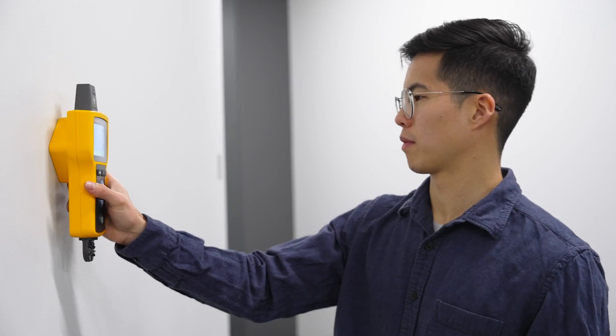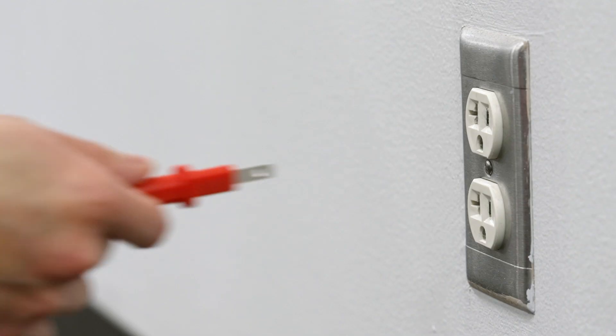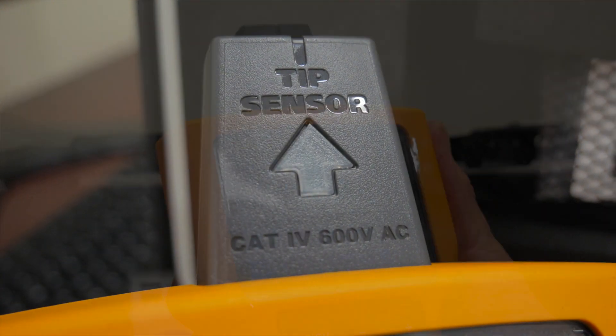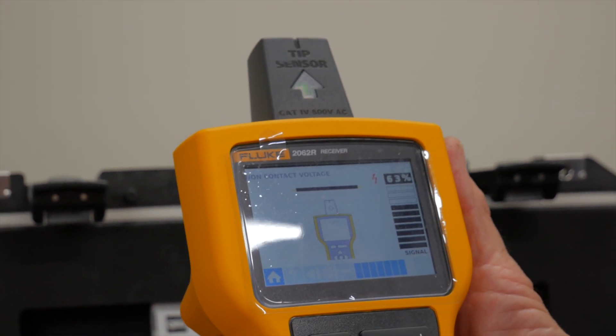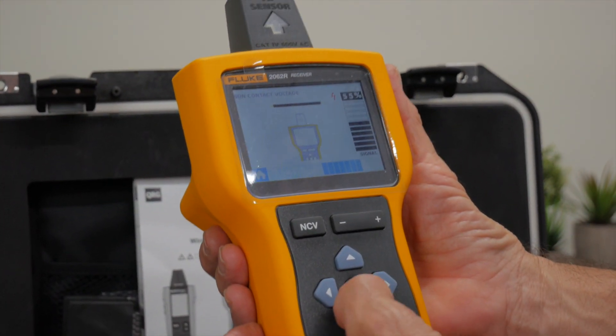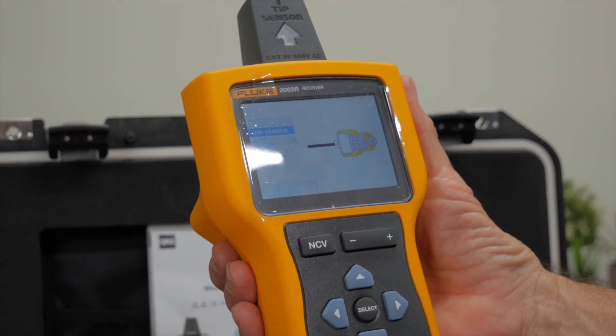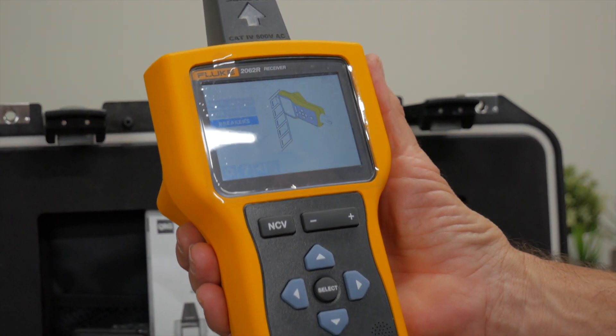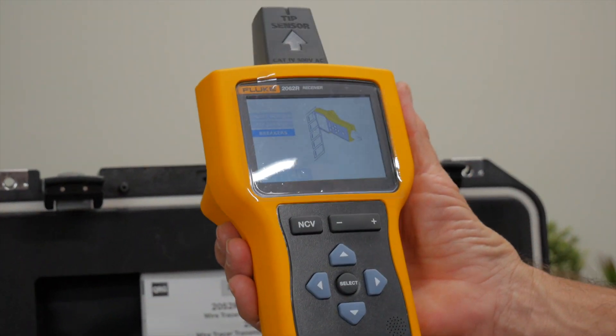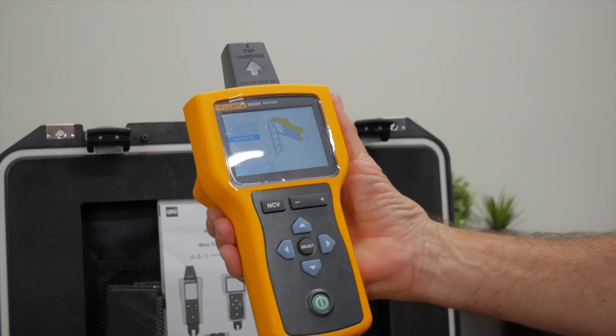We're going to do a combination of two things using the smart sensor technology, and we're going to use the transmitter to actually put a signal into your outlet or an electrical connection like in a breaker box, for example. This tip sensor is actually a voltmeter and it's going to be able to pick that up. Additionally, in the menu mode is the ability to use what's called the tip sensor by itself, and we would actually trace it that way. The other mode that many people are using is what's called a breaker panel mode — I would hook my transmitter down here with a connection going into an outlet, and then walk back to my breaker panel and be able to identify where that outlet is in terms of which breaker it's attached to.